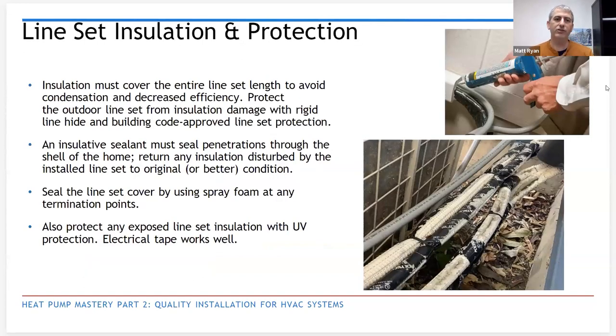Yeah, a little bit more here on just the insulation and protection. Cover all of that copper and brass components. It's actually becoming code now. In that bottom photo, you can see the UV's really chewed up that insulation that comes with the line sets. We kind of learned that lesson the hard way on a couple commercial settings. There's a lot of good products out there to wrap those lines. Just making sure we're protecting those, making sure those holes are all sealed up. Just good building practices there.